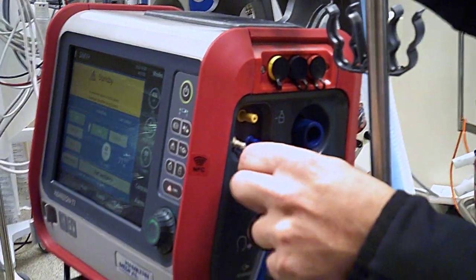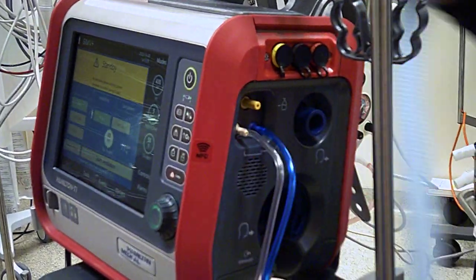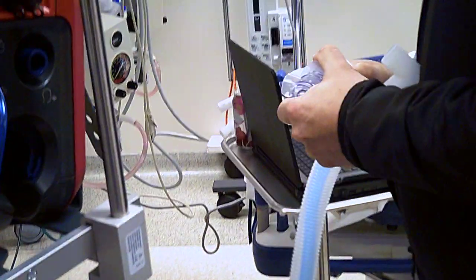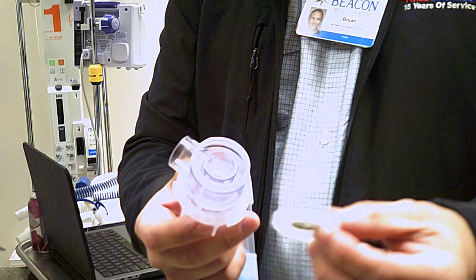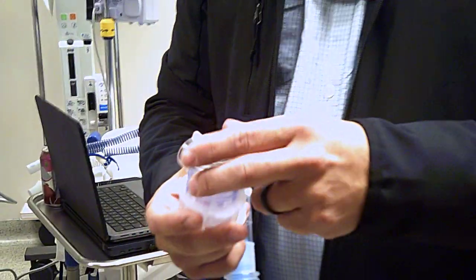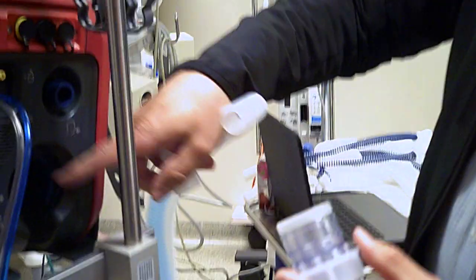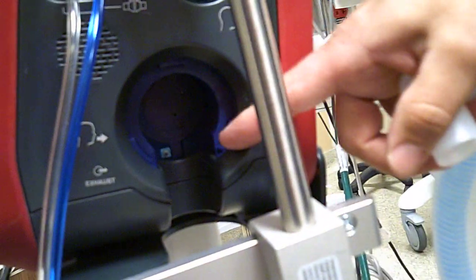Right, this is easy. Blue to the blue. Clear to the white. I'm missing my dial. Oh yeah, he noticed. So this is a good point, I'm glad this happened. It happens all the time, sometimes these diaphragms come off. And oops, here that is. Pull off. Make sure it's clean. So another good point too is look in here and make sure there's not another diaphragm stuck in there because that has happened.